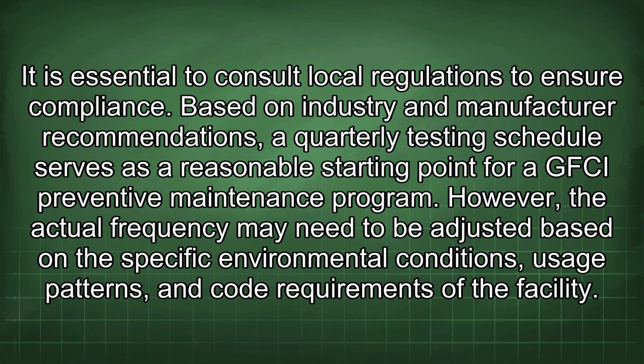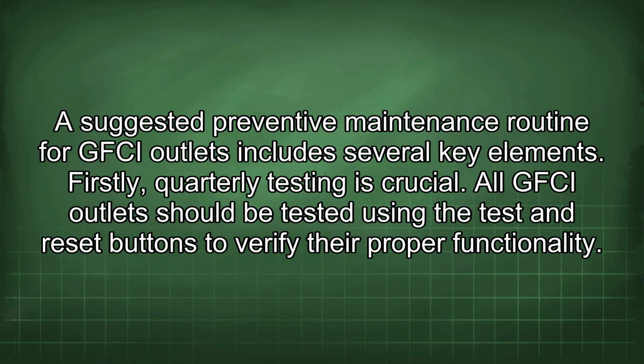Based on industry and manufacturer recommendations, a quarterly testing schedule serves as a reasonable starting point for a GFCI preventive maintenance program. However, the actual frequency may need to be adjusted based on the specific environmental conditions, usage patterns, and code requirements of the facility. A suggested preventive maintenance routine for GFCI outlets includes several key elements. Firstly, quarterly testing is crucial. All GFCI outlets should be tested using the test and reset buttons to verify their proper functionality.